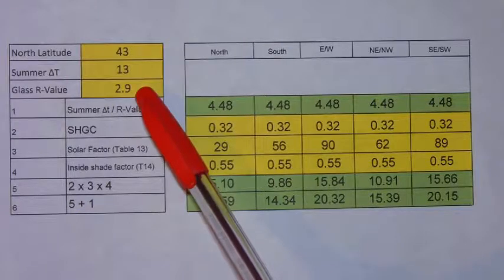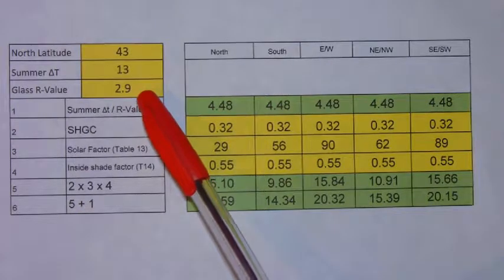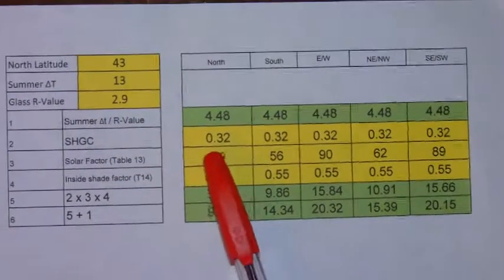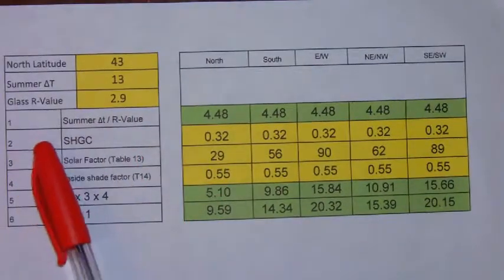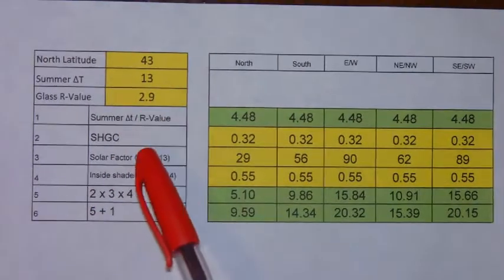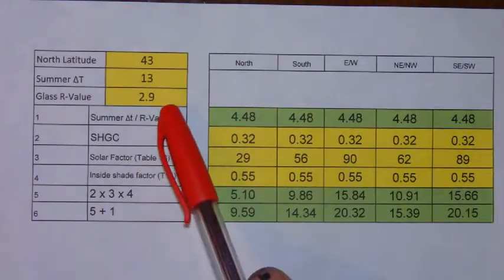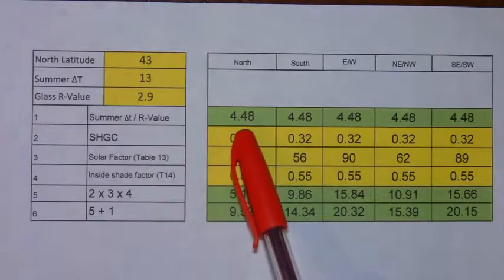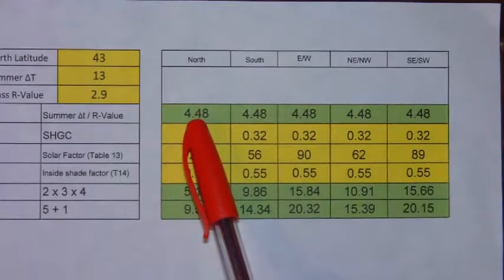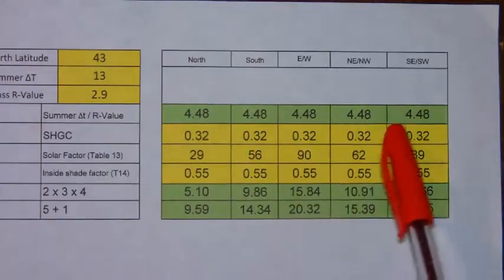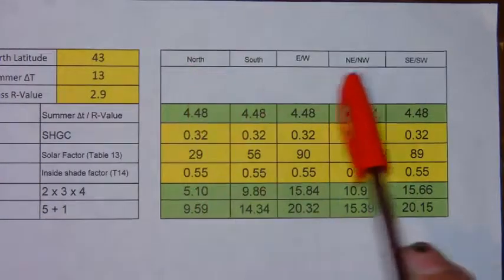The glass R value can be obtained from page 3. The first step is to take the summer delta T — in this case 13 — divided by the glass R value which is 2.9, and that gives us a factor of 4.48 for all the different directions.